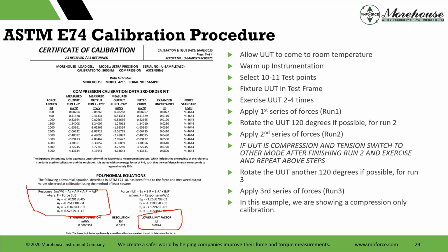Basically, I'm going to add additional error by doing that. And we see a lot of people take these reports and then they go program them into something. Fine. It's just you're going to have additional error. When we talk about derating the device, that's additional error that you need to account for. So the lower limit factor is giving you that expected performance. Then you're not using the equation. And by not using the equation, you really can't go back on that lower limit factor unless you say, hey, in addition to that lower limit factor, I know I have this additional error of 0.02% or whatever that error may be. So now I've got to take my expected performance, I've got to take my other errors, and I've got to figure out my uncertainty that way. So the best thing to do is to use this equation. By using this equation, you can almost guarantee that expected performance is going to be somewhat repeatable if you're using the right adapters and everything else along the way.